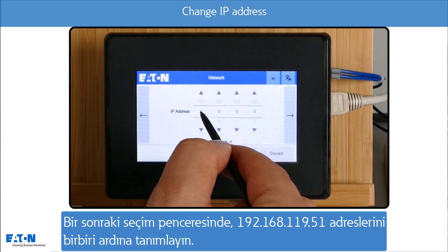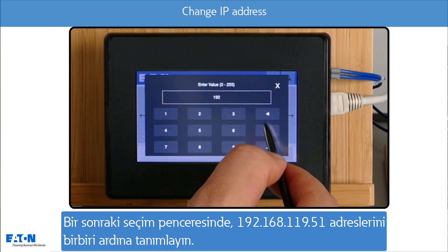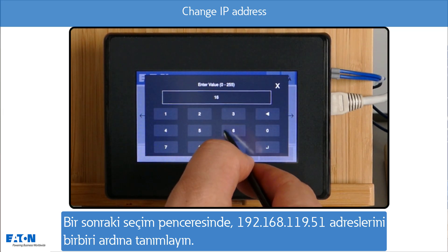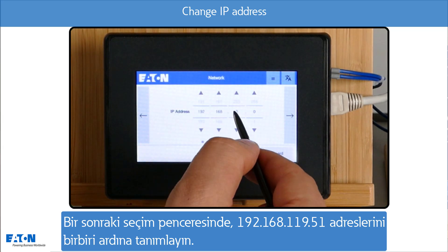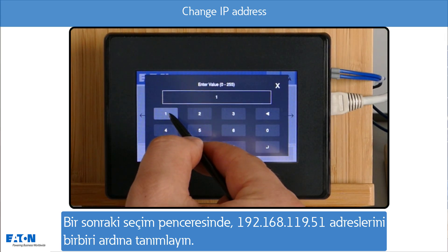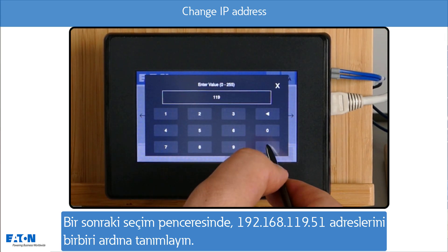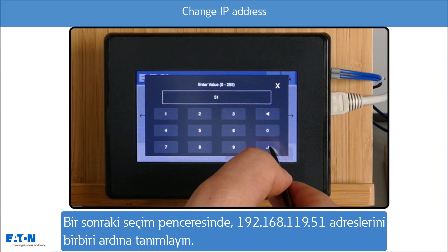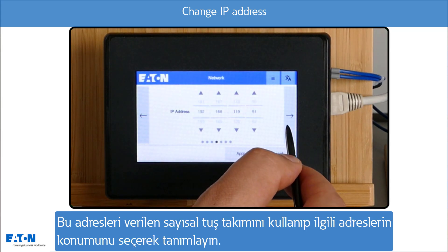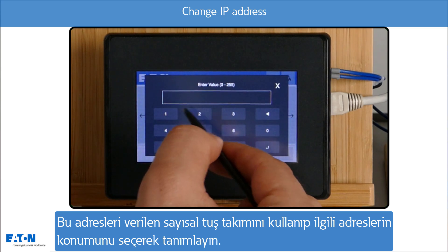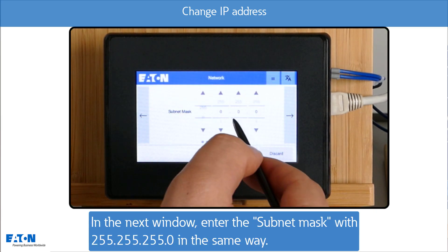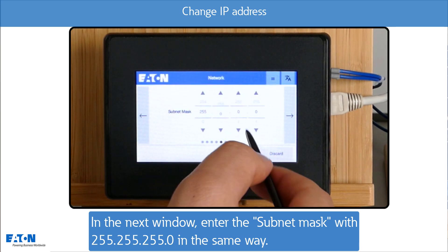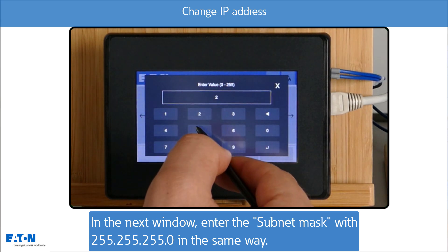In the next selection window, the address 192.168.119.51 is defined one after the other. This is done by selecting the corresponding address location using the numeric keypad provided. In the next window, enter the subnet mask with 255.255.255.0 in the same way.